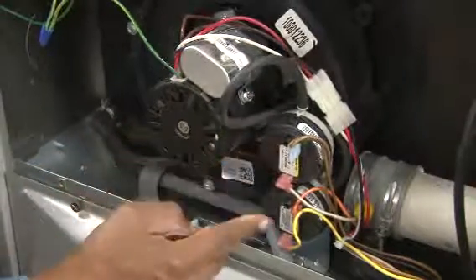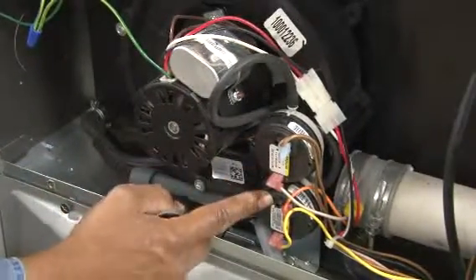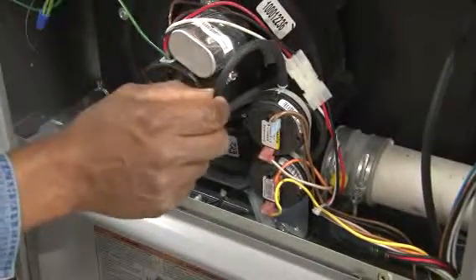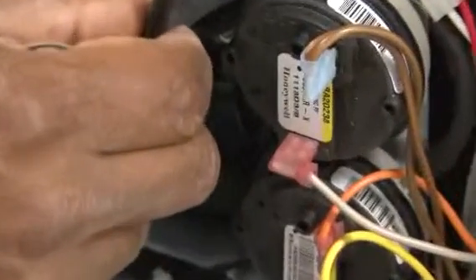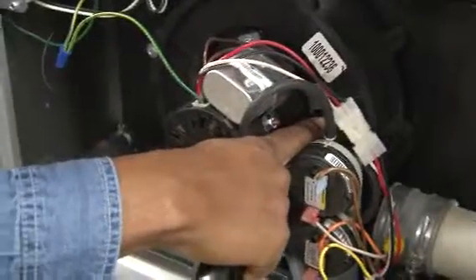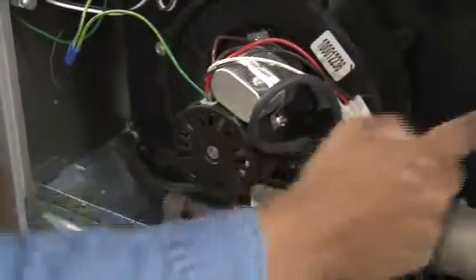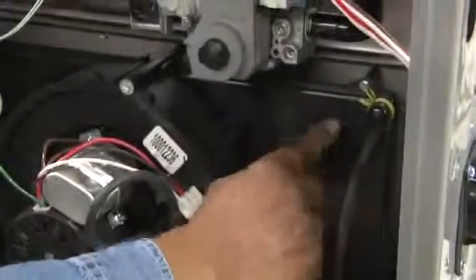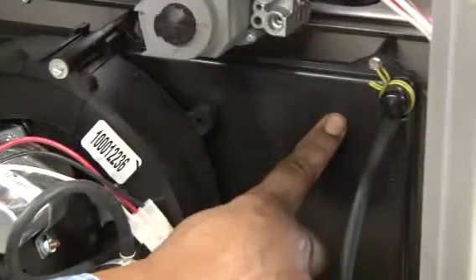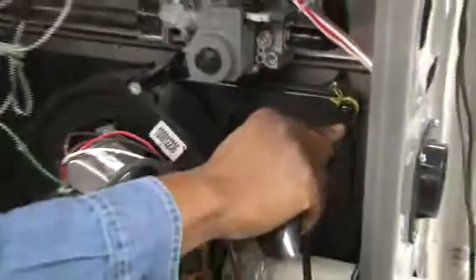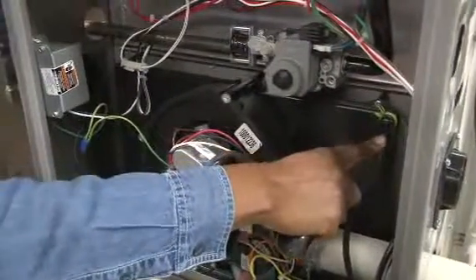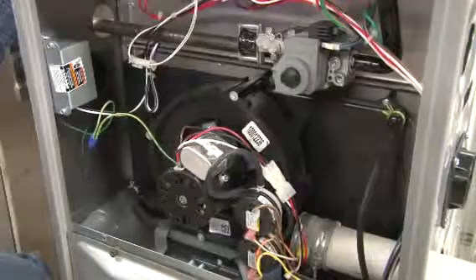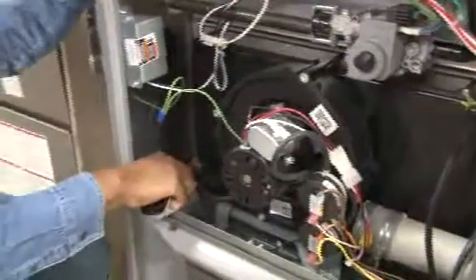This particular one has two different pressure controls. One to sense positive, and another one to sense negative pressure, and they're connected to different parts of the combustion chamber. One is here connected to the induced draft blower motor, the blower itself, and the other one is connected to the secondary heat exchanger collector box, to sense the pressure there, to sense the airflow through the combustion chamber. And you see another one located at this portion of it.